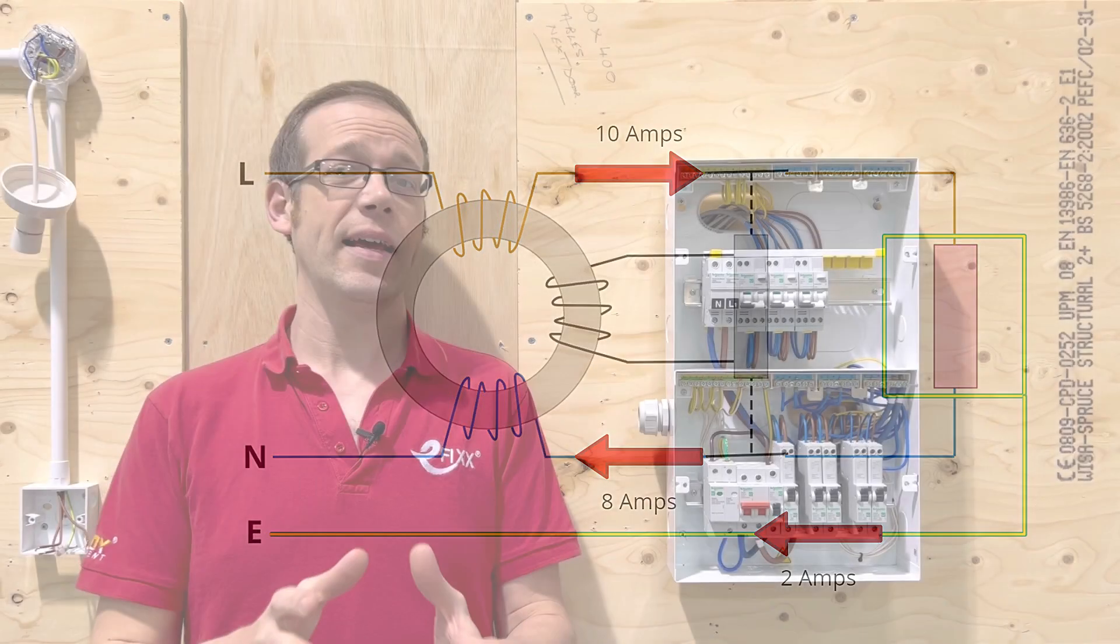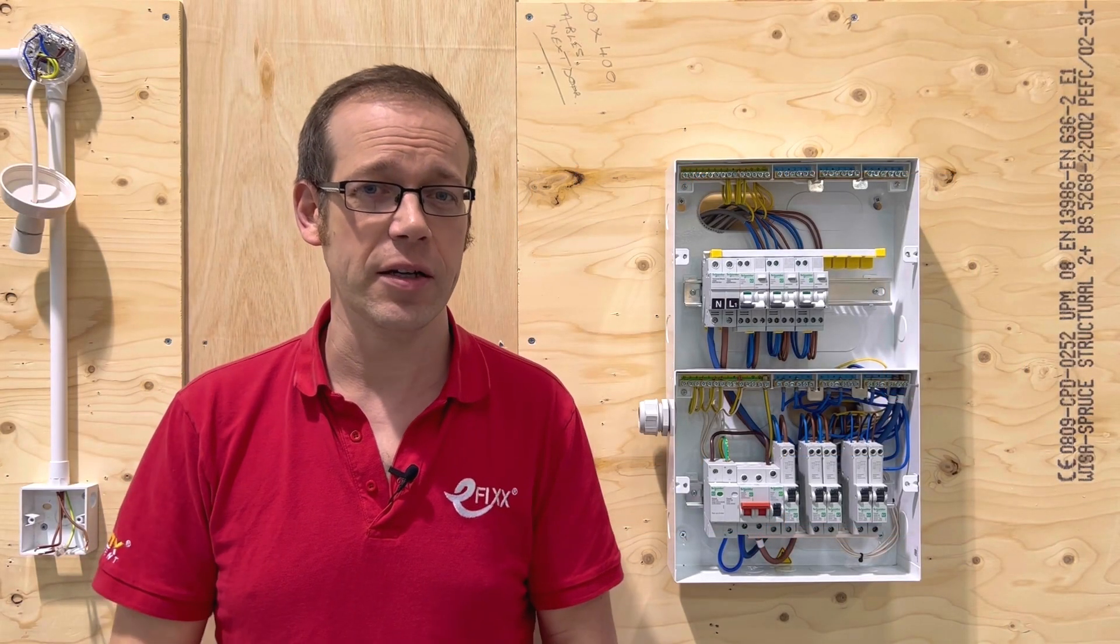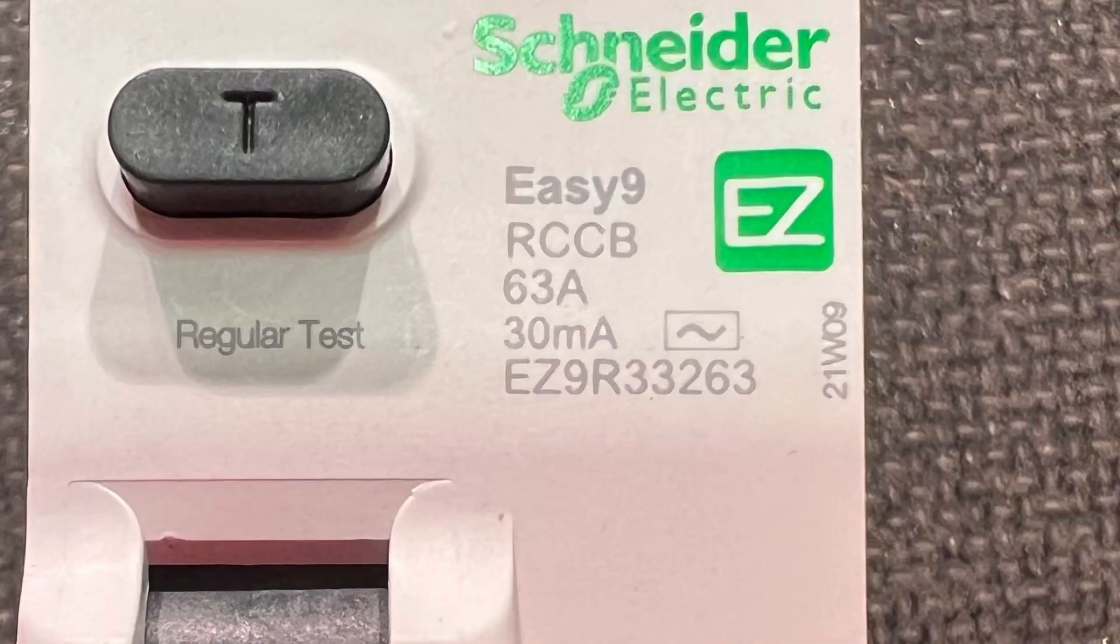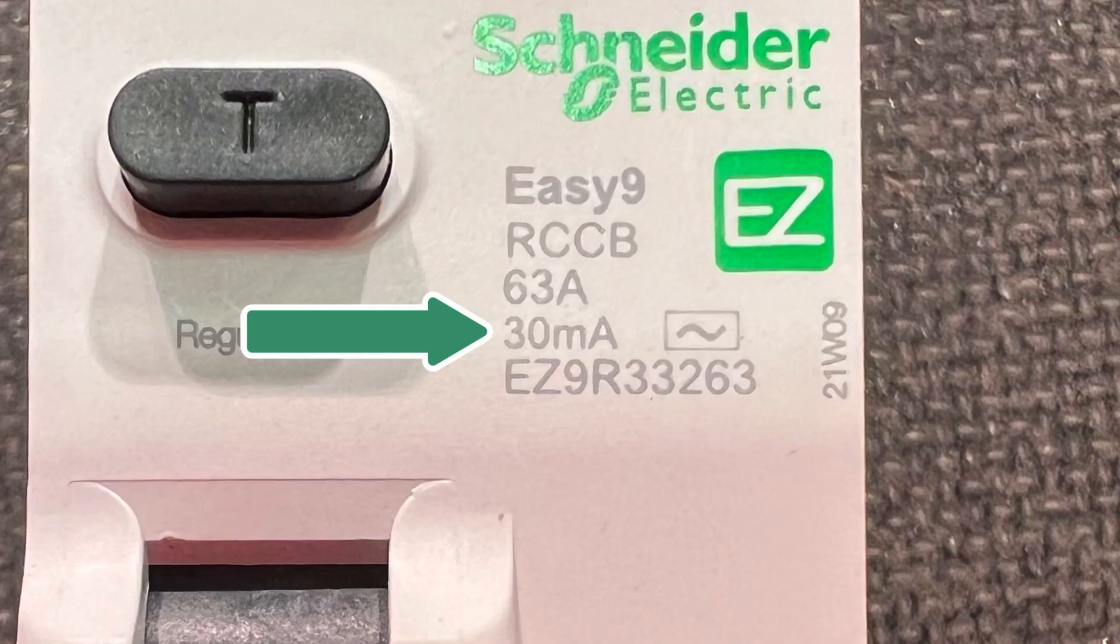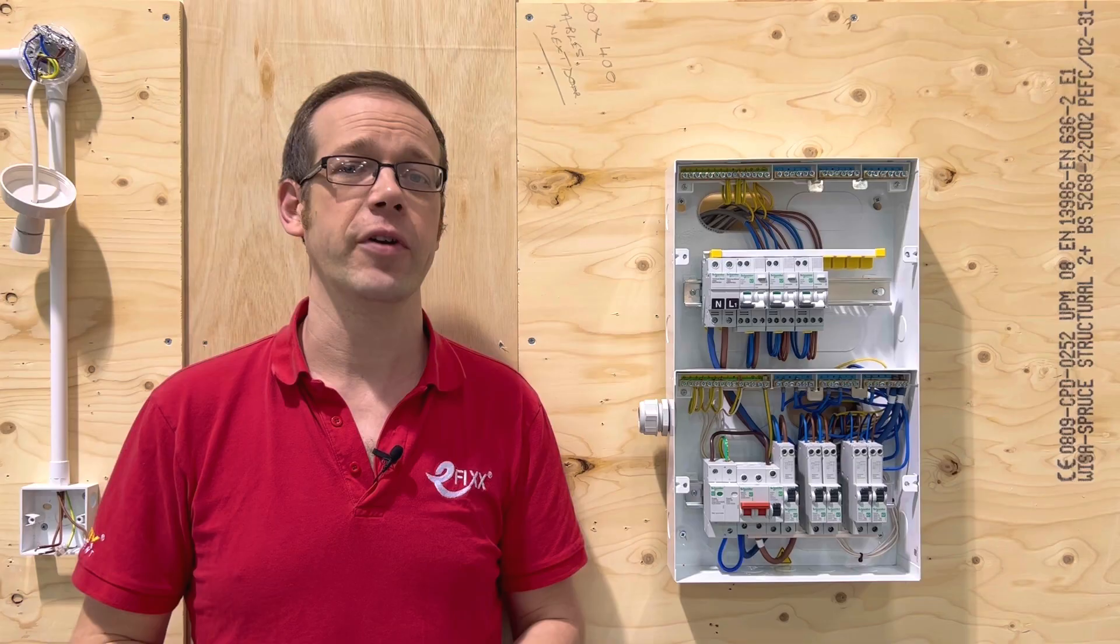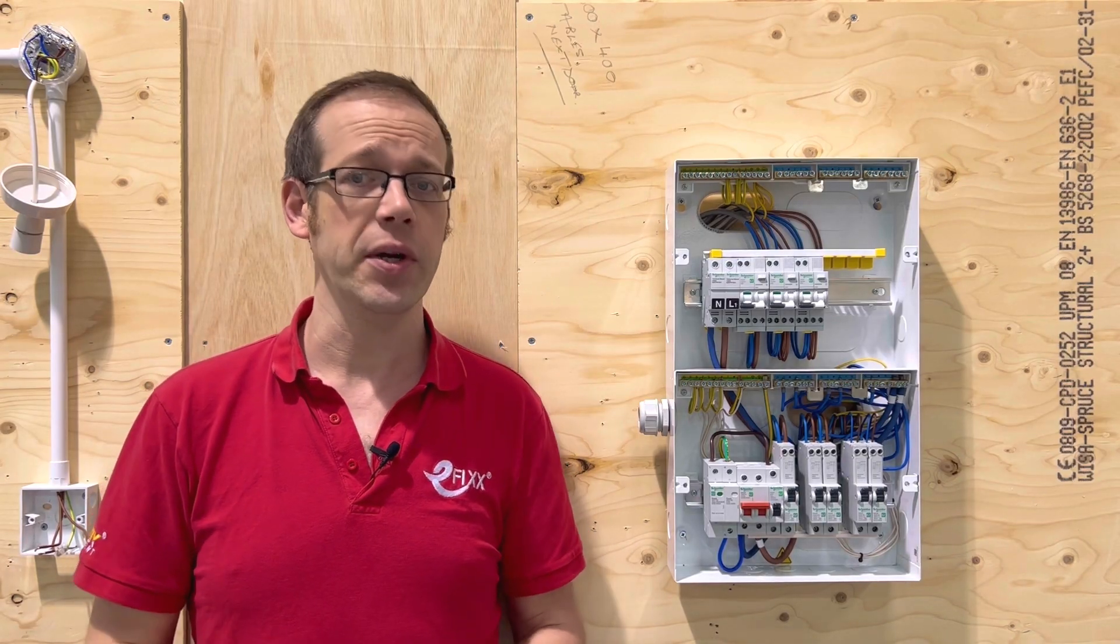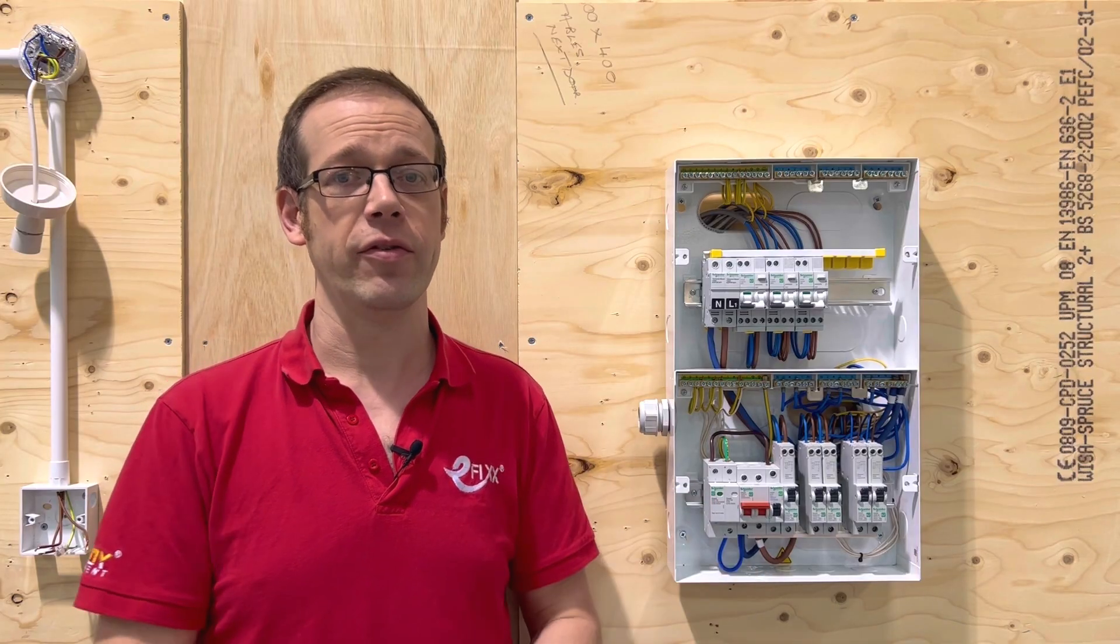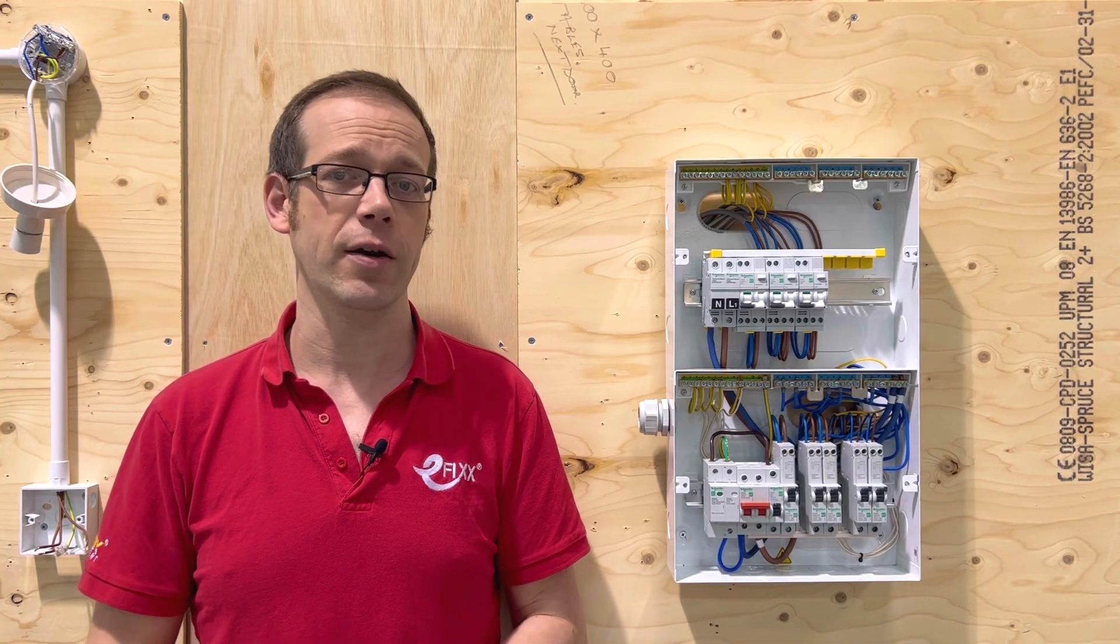An RCD can detect absolutely minute differences in current. For a device offering additional protection this current will be as small as 30 milliamps or 30 thousandths of an amp. That's a microscopic amount of current. It's usually considered that it takes 50 milliamps of current flowing across the heart to kill a person. So an RCD won't allow this amount to flow through a person to earth and could therefore save the life of someone receiving a shock.